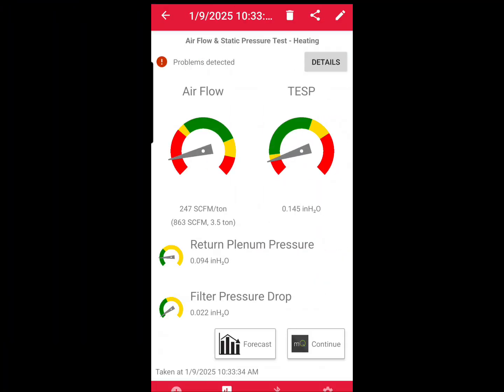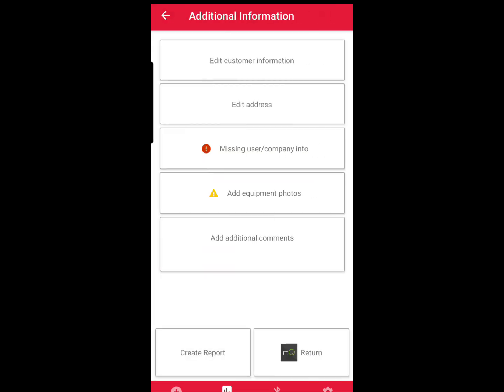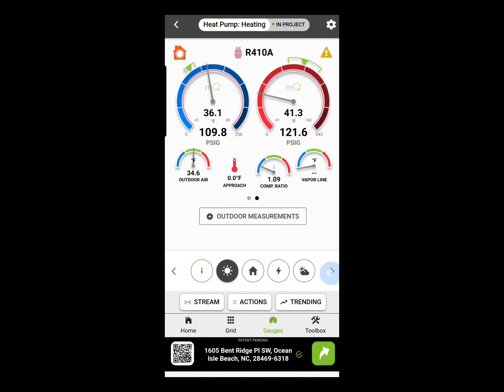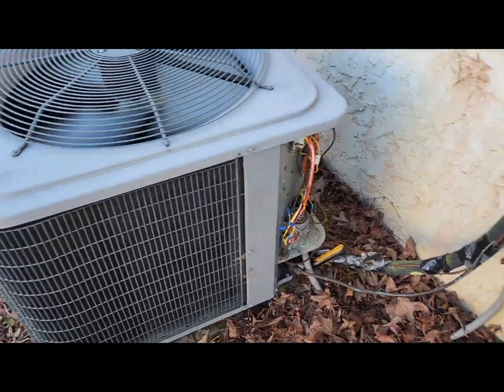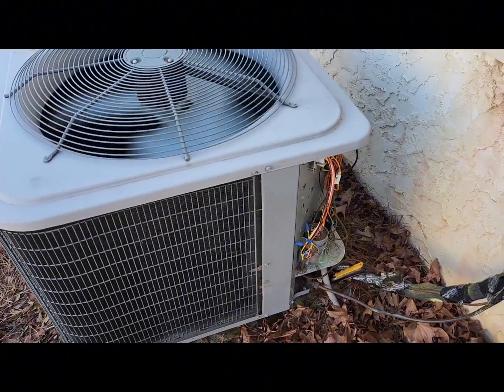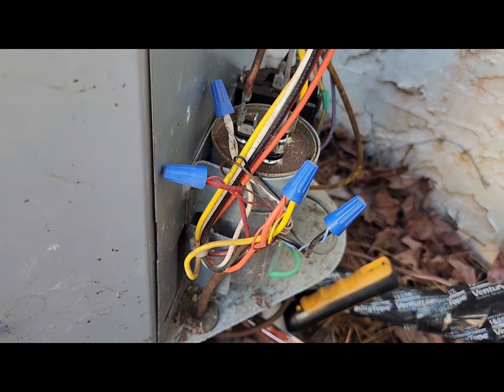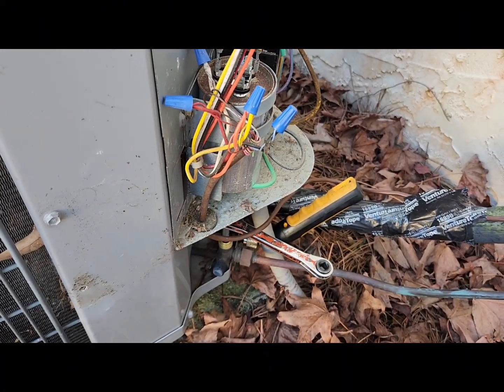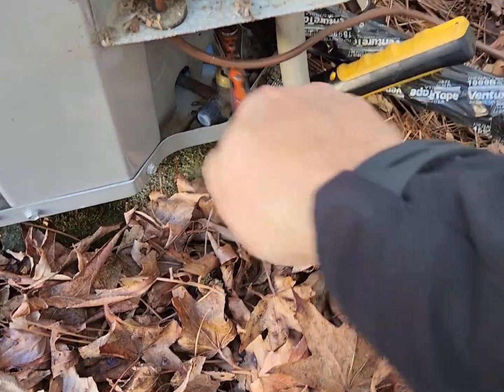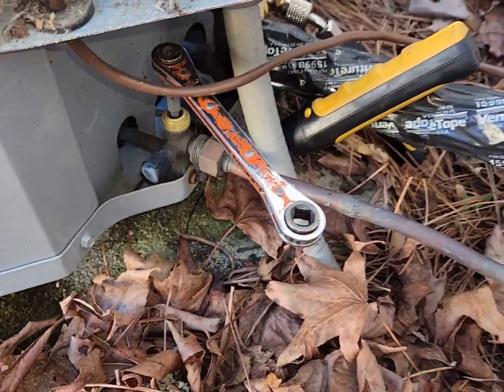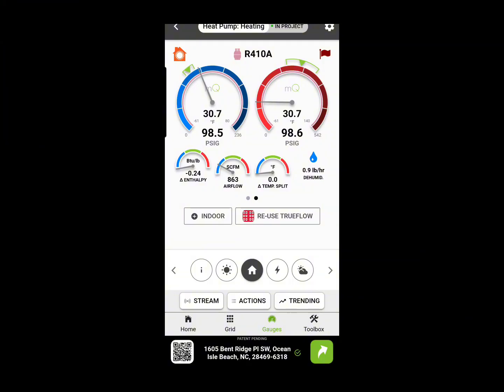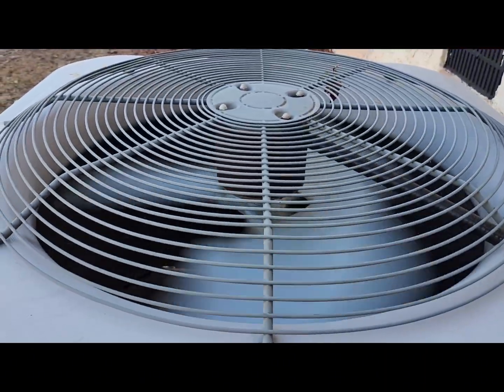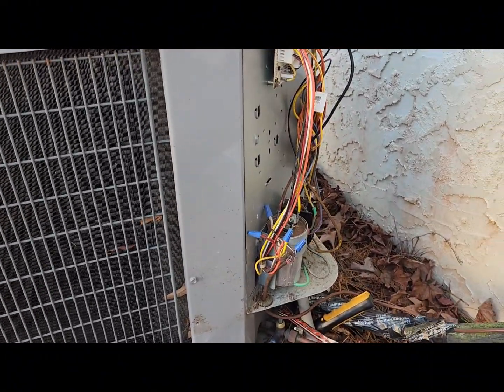I've got airflow problems and low static pressure — which is a little surprising, but the dirty blower wheel may explain that. But as it talks back to MeasureQuick, I notice something else: my pressures are not changing between low and high side, so there's really not a lot to diagnose — I don't have any compression ratio. It looks like we've got a compressor that is no longer pumping. To verify that, I do a quick pump-down test. I jump O and Y together to put it in cooling mode — there was no whoosh, confirming no pressure difference between suction and high side. Closing the liquid line down, the pump-down test confirms it: we've got a compressor that simply is not pumping. It has failed.